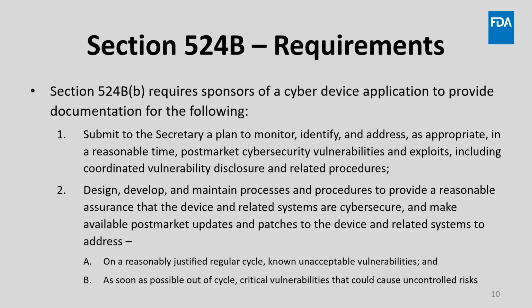It also requires manufacturers to provide documentation on how they design, develop, and maintain processes and procedures to provide a reasonable assurance that the device and related systems are cyber secure, and to make available post-market updates and patches to the device and related systems to address on a reasonably justified regular cycle known unacceptable vulnerabilities, and as soon as possible out of cycle critical vulnerabilities that could cause uncontrolled risks.